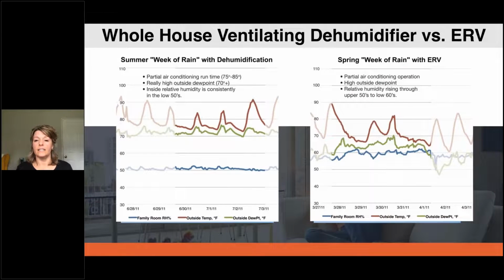This was in Orlando, a house, the NHB Emerald Green house, that had an ERV in it, and they were experiencing, as you can see on the right side, that blue line is the RH in the family room, consistently above 60%. That green line is the dew point outside, so the relative humidity in the home was following basically that dew point outside.